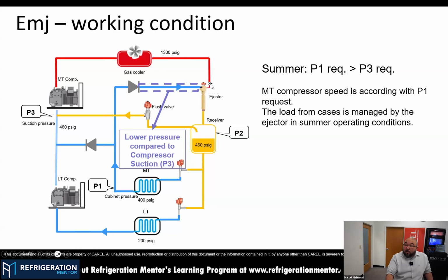So it means I have a lot of energy to be transferred to the suction line. So I have a low pressure zone here. And the preferred path for the MT flow will be going from the cabinet to the ejector port. So during summer, I can also get 100% of the flow from all my MT cases, evaporators, cases, walk-ins, going to the ejector port here. So I'm having a free compression.